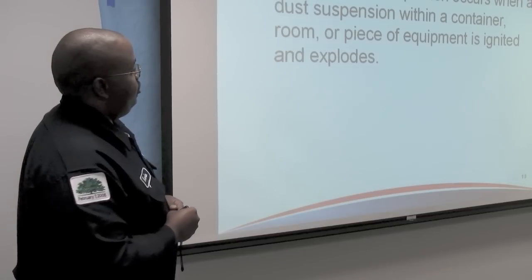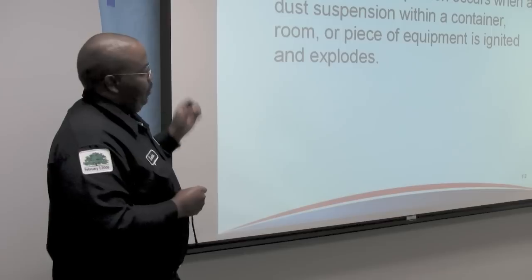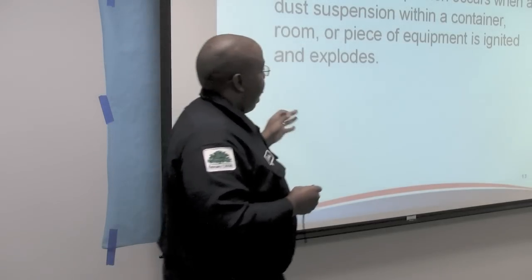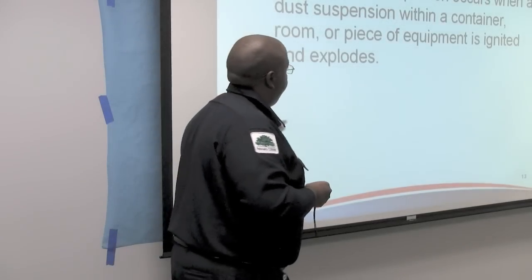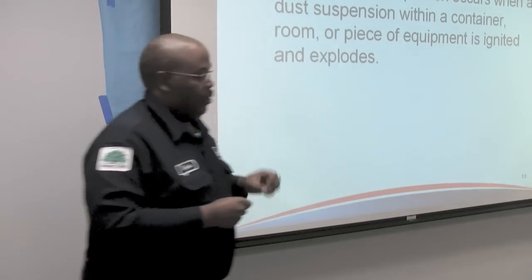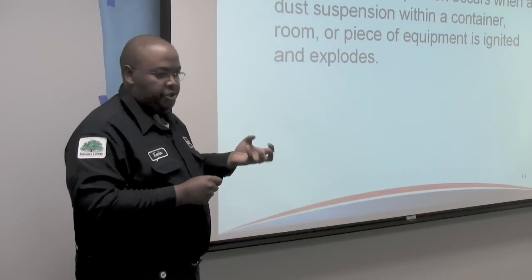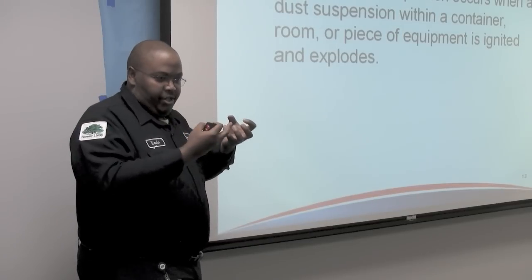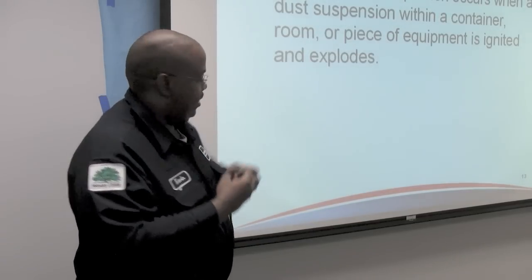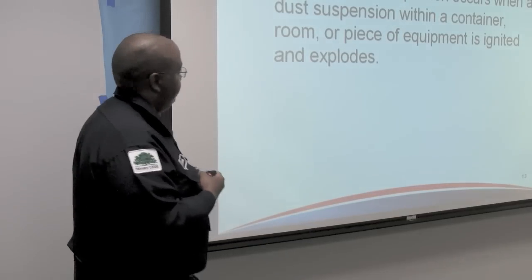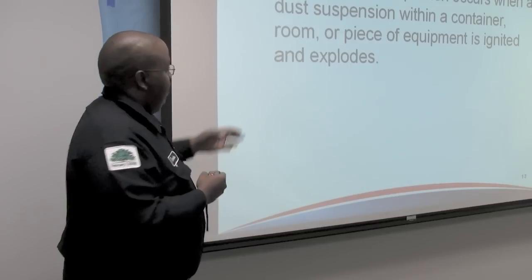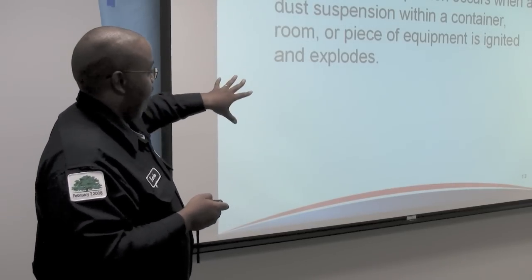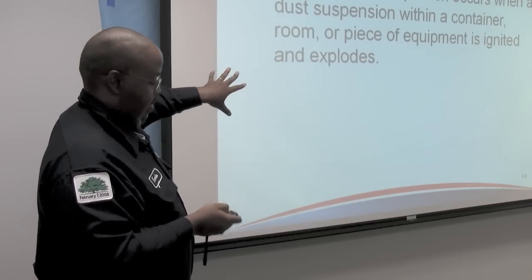Types of combustible dust explosions: you always have a primary explosion. That primary explosion occurs when there's a small-scale suspension that meets a source of ignition and you get that deflagration — in a small piece of equipment or a room.